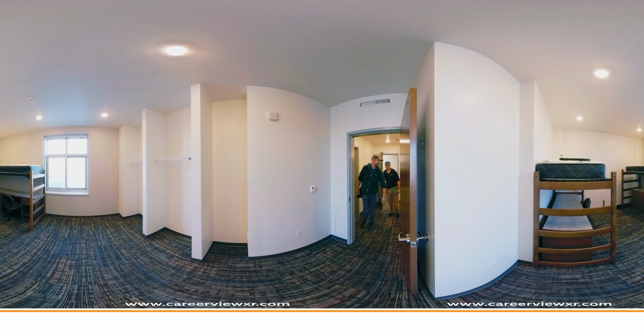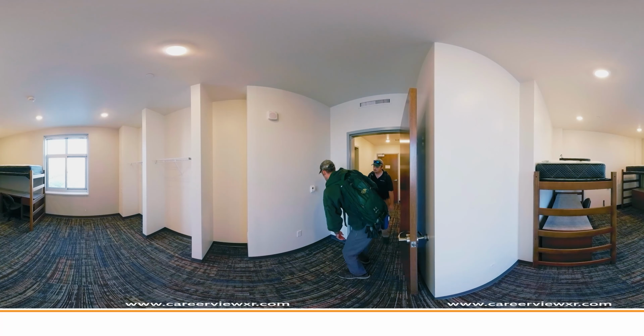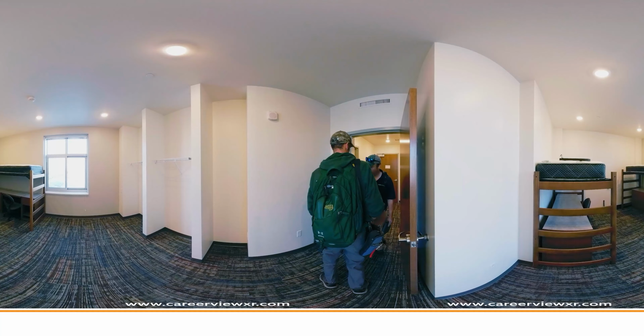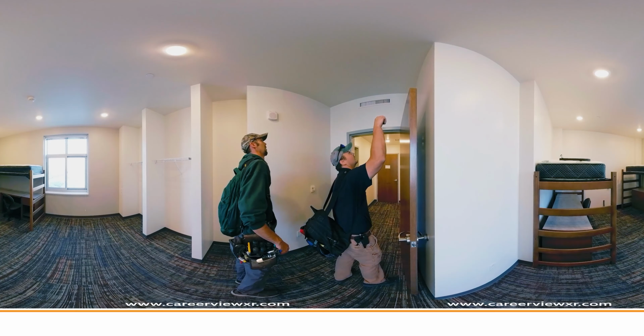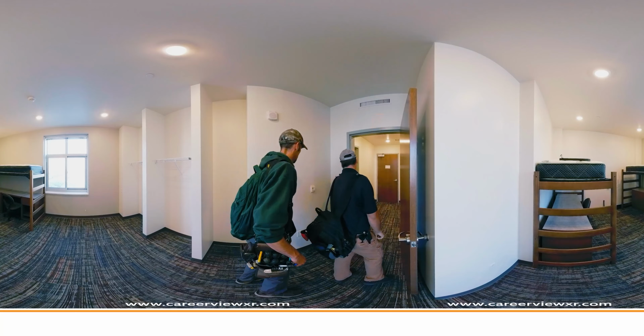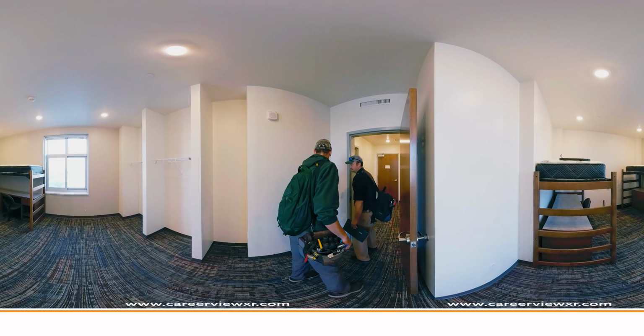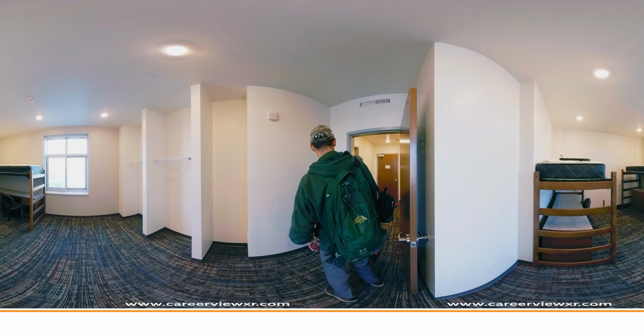Andy and Mike are checking on a heating-cooling issue in a room at Catherine Cater Hall. The work order stated that the room was very cold. The thermostat temperature reads well below the set point. Mike uses the IR temperature tool to read the temperature of the room. It is 52 degrees. The room temperature matches the thermostat, so they know the thermostat is reading correctly.